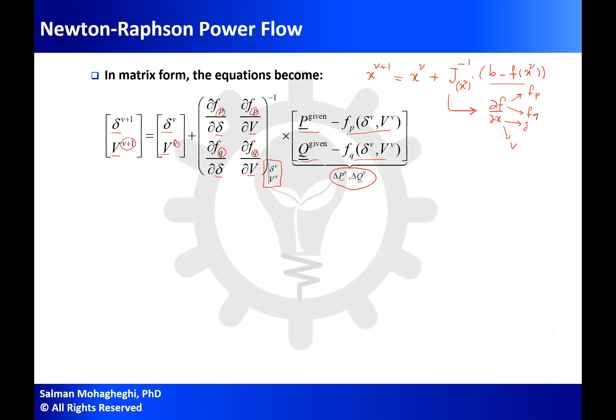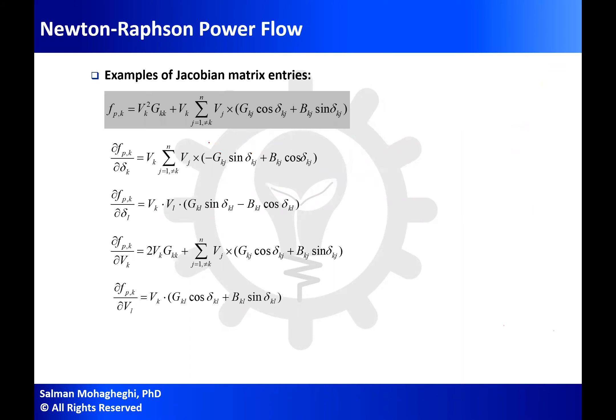Formulating the Newton-Raphson power flow is quite simple. All you have to do is find the derivatives of those equations with respect to deltas and Vs, update the values based on the latest delta and V, invert that matrix, and multiply by that vector. For a small enough system you can find the derivatives directly; for a larger system you do this parametrically. Let's go back to the equation for active power.